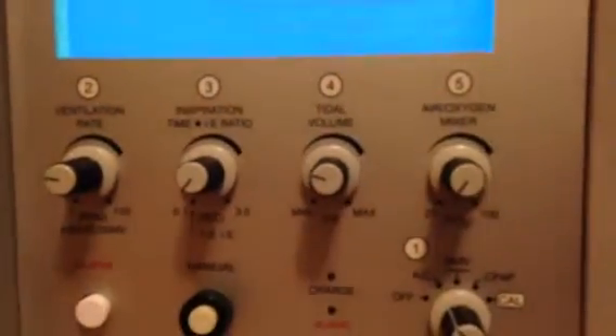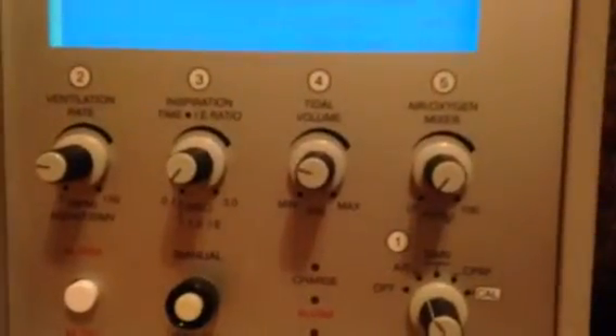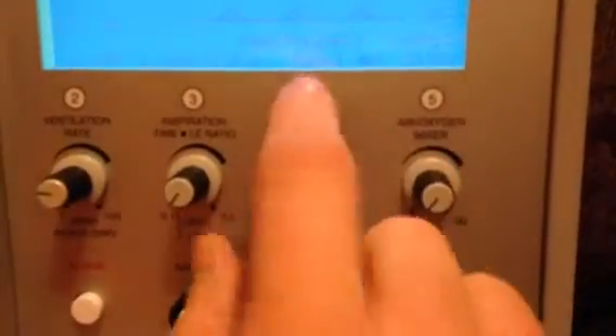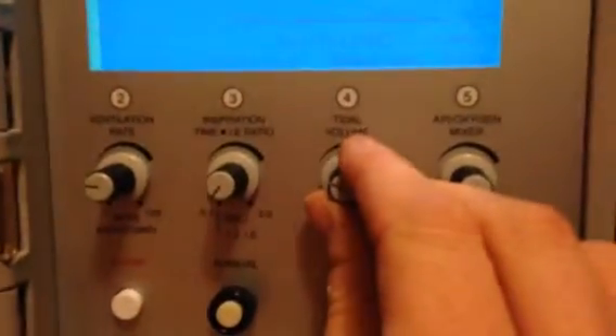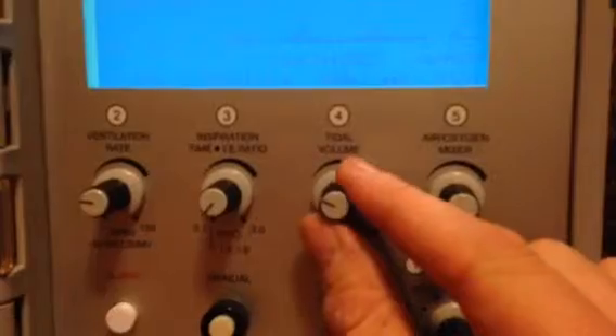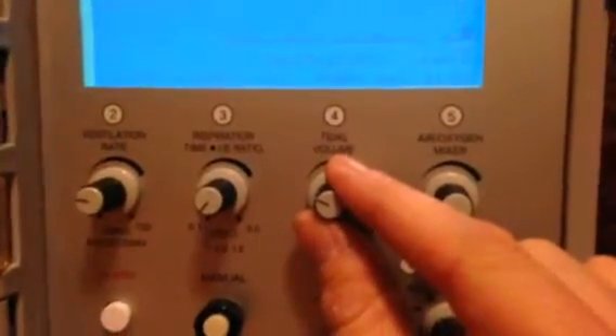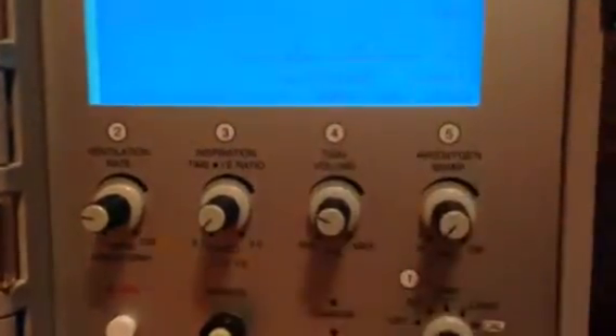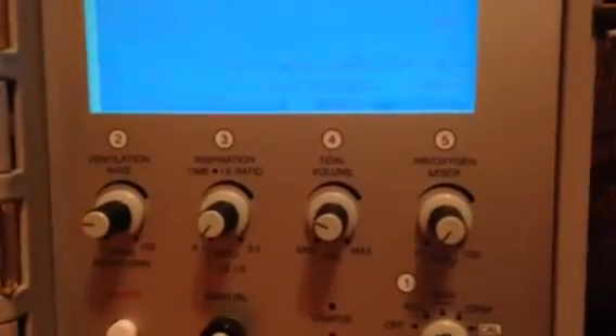Step 4, we're going to set the tidal volume. This is the amount of air that the ventilator is going to deliver to the patient in one respiration. Right now you can see it's set for 550 and it's delivering. It'll show you what it delivers. It delivered 546 milliliters. So we're going to set this tidal volume to 600 just so you can see it working. If you can see, I barely touched the knob. So these knobs are really sensitive. They're going to be hard for you to adjust when you're transporting.